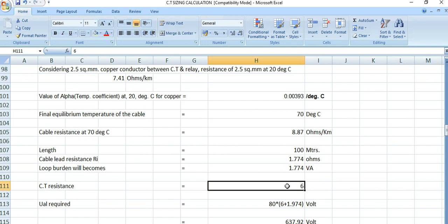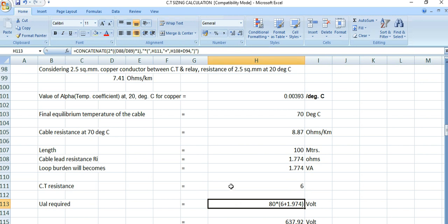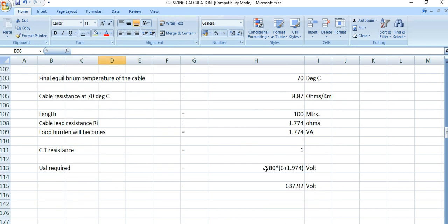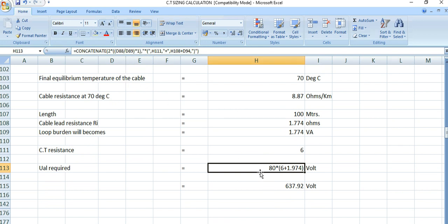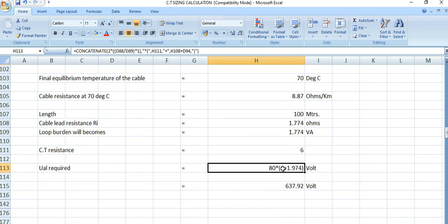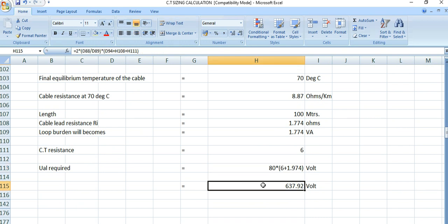The CT resistance will be provided by the CT manufacturer — you can get the CT resistance value from them. The knee point voltage V_k is calculated as: twice into IF/CT ratio, which is 2 into 40 kilo ampere divided by 1000, into (R_CT of 6 ohms plus loop burden 1.774 plus relay burden 0.2). After calculation, the required knee point voltage is 637.92 volts.